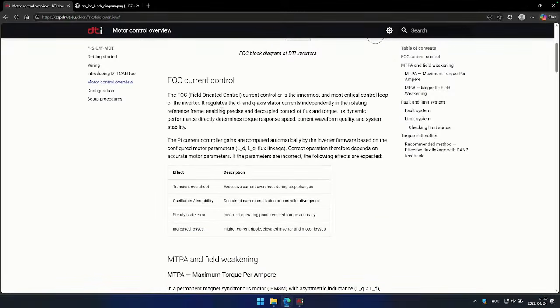So the current controller has to be tuned properly, but this tuning in the case of the DTI inverters is not necessary, because the PI current controller gains are computed automatically by the inverter firmware based on the LD and LQ parameters, so Q inductance and D inductance.